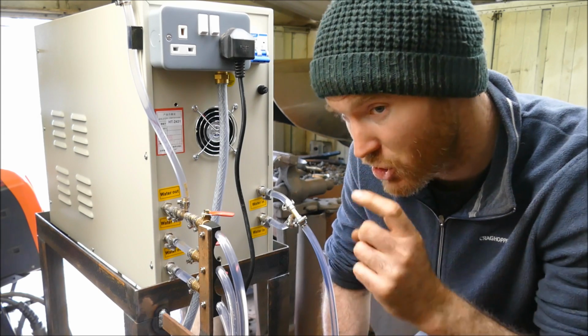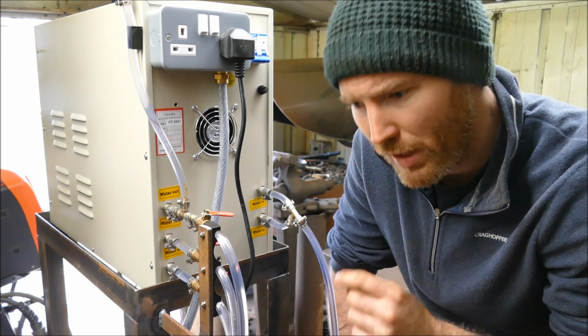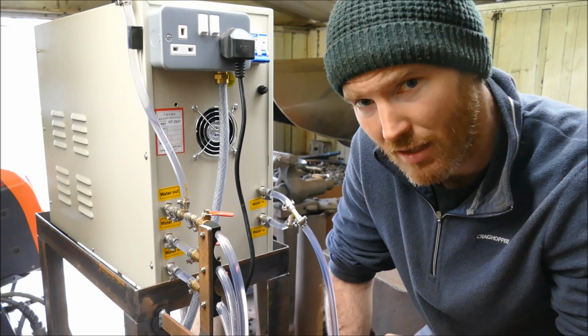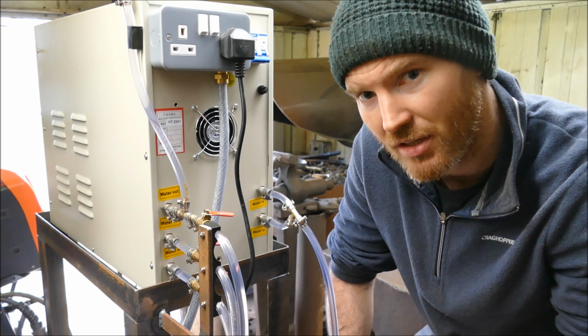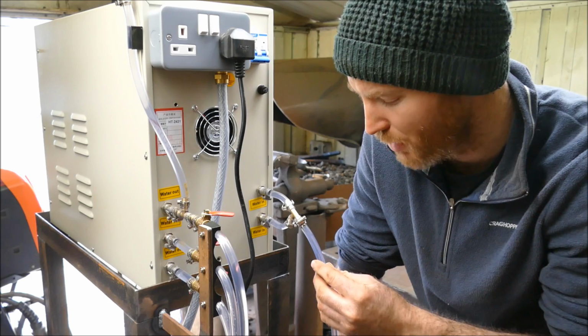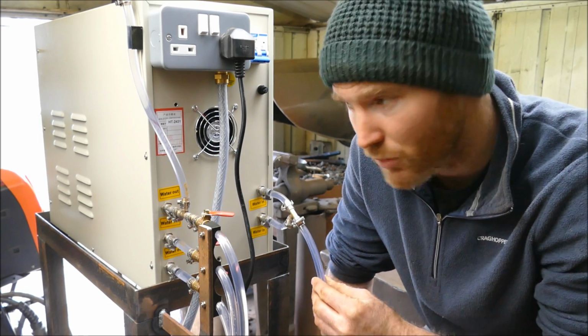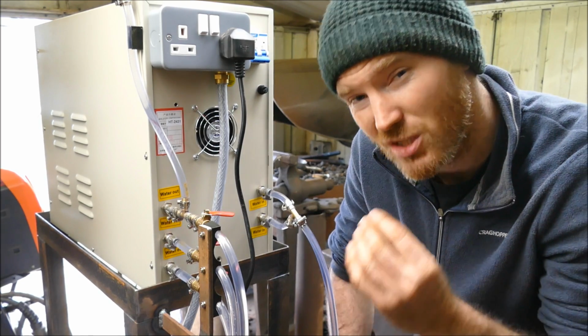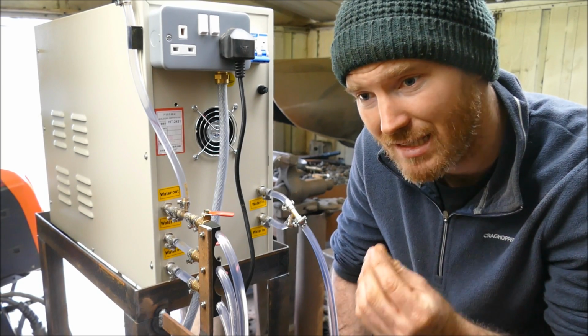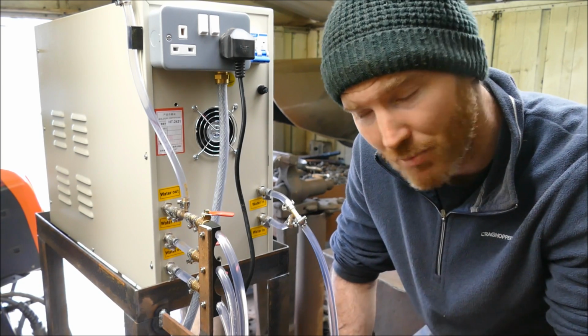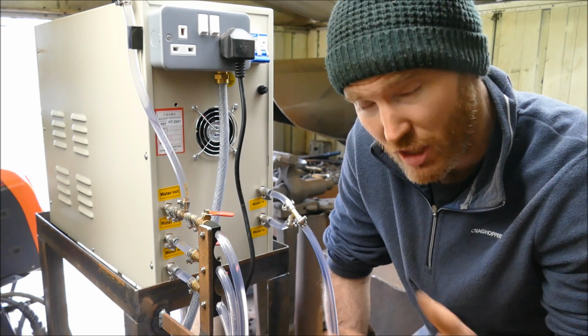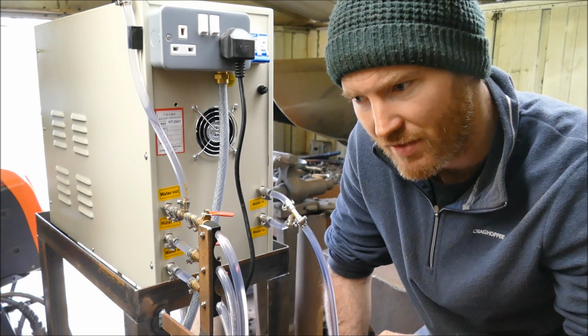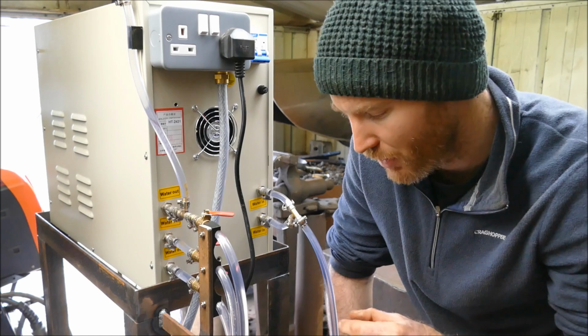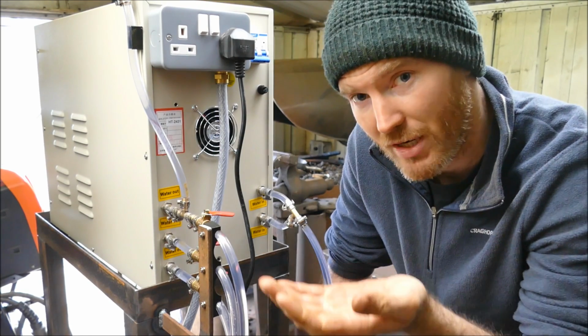certain things. The chiller that I have chosen will produce the correct PSI, but only under certain conditions. So if you use pipe that is too big, it will simply not be enough pressure. It needs 20 psi running at 6 litres per minute minimum. So it has to be above that. The chiller is fine itself and I love all the safety features, but I might have to change the pump over just to get that pressure rating up.